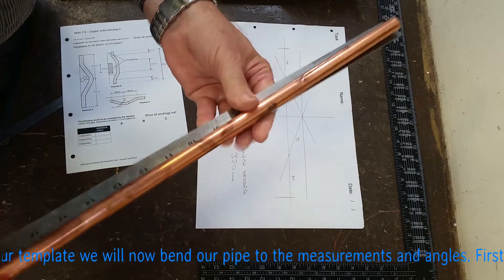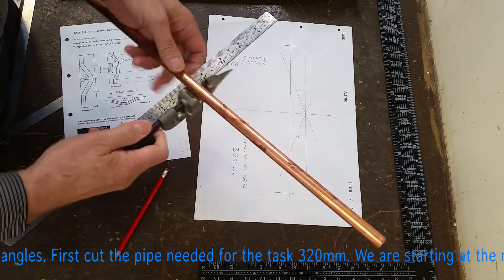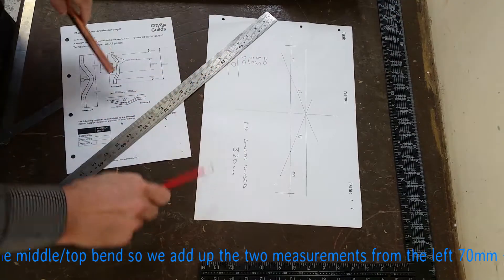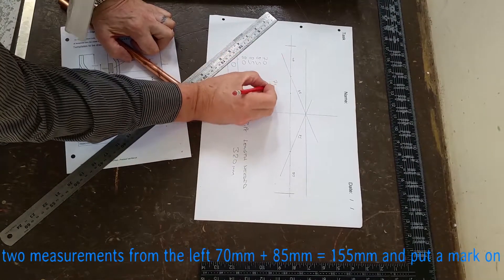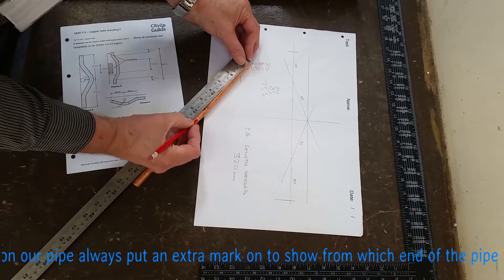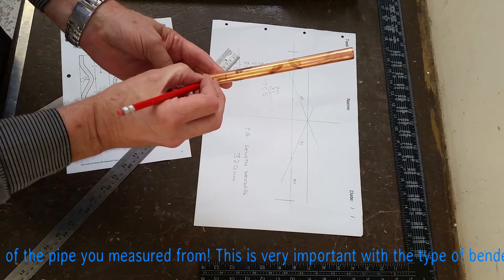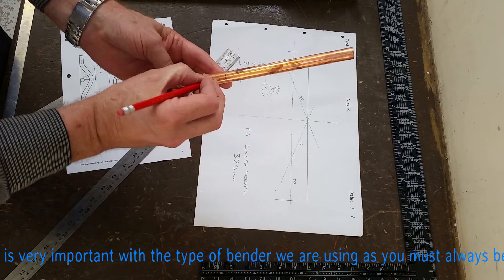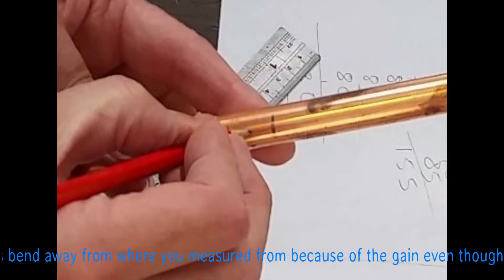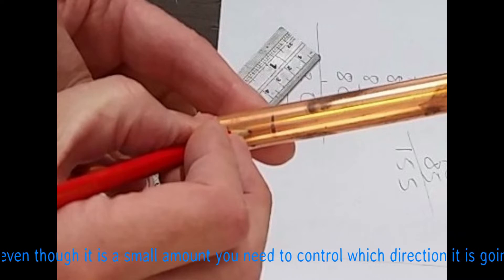Measure your pipe, 320mm, cut your pipe. Now, remember when you're dealing with doing bends in a bender, you always need a straight bit of scrap pipe to find the angle using your angle ruler on your bender. So add up your first two, because we're going to start with the second bend, not the first bend from the left. So that would be 70 and 85, which is 155. Mark that on the pipe. Now, make a little mark where you measured from. In this instance it doesn't really make a lot of difference, because we're bending from the middle outwards anyway. But on a complicated bend later on, you must always bend away from where you measured from. So if you get in the habit of putting a little mark on your pipe, if you put it down and pick it up again, then you'll always bend it away from where you measured from, and then any gain will go in the direction you want it to.